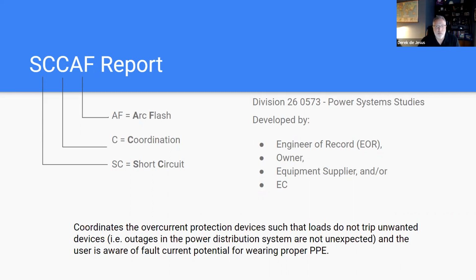Okay, so another opportunity for validating the SCCAF study accuracy is something called factory witness testing or integrator witness testing. A lot of times you'll hear contractors testing breakers in the field, at the project site, and there's reasons for that. Jostling or handling of equipment, the breaker could get damaged as it gets shipped from the factory to the site, and they want to test it once. They want to make sure it works. But there is an opportunity at the factory or at the integrator to take that SCCAF study and validate we have the actual model, manufacturer, and frame rating correctly.